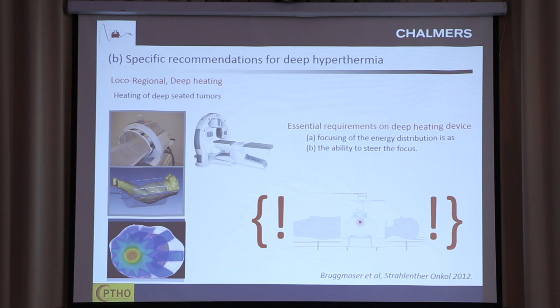prefers the radiative devices, because here we can really nicely steer the energy within the treated volume. Users of capacitive systems should be aware and careful, because this ability to steer the focus is somewhat limited. The only possibility to steer the focus here is to use the smaller electrode on the top, and then we can steer the focus up and down. So just be aware of this.